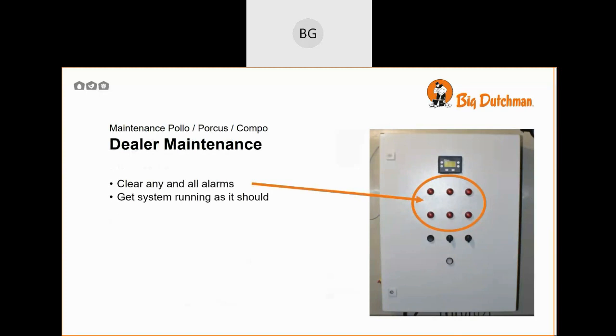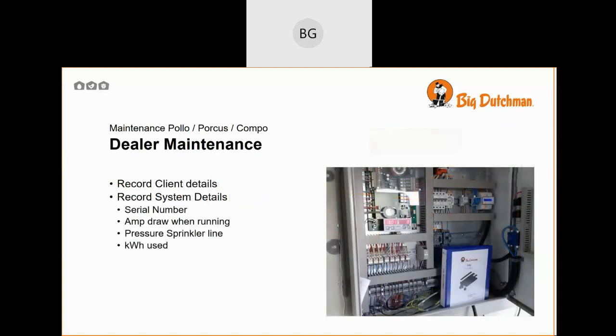Dealer maintenance. The first thing that we'll cover in dealer maintenance is that you'll need to clear any alarms and get the system running as it should. Record the client's details. We'll need to record the system, the serial number, the amperage draw across each phase of the pump when the system is running, the pressure on the sprinkler line, and the kilowatt hours used.